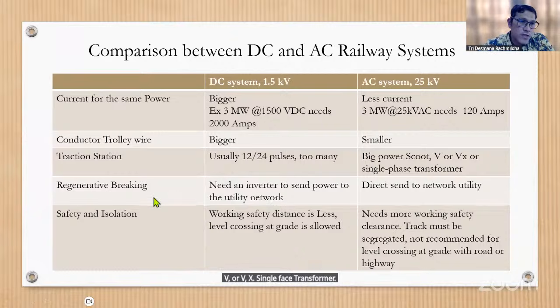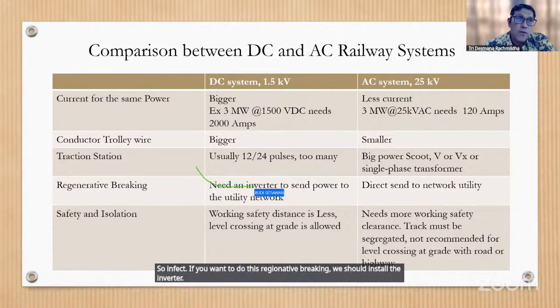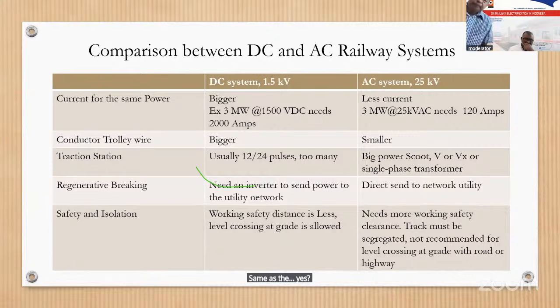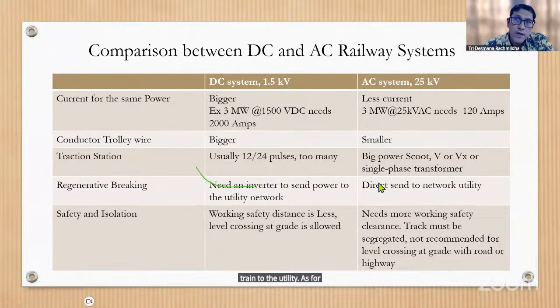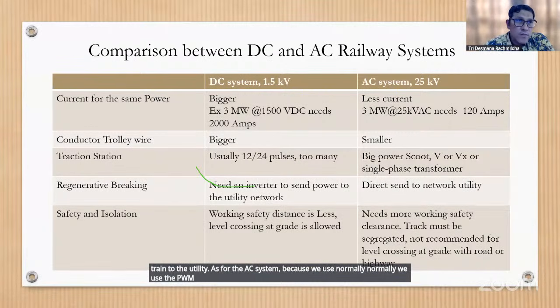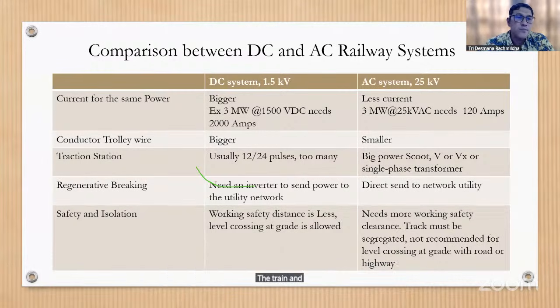And as for regenerative braking in the DC system, because normally we use diode-based rectifiers, it is not possible to do regenerative braking. So in fact, if we want to do regenerative braking, we should install an inverter to send power from the train to the utility. As for the AC system, normally we use PWM rectifiers, PWM converters, so it is possible to have bidirectional power flow between the train and the catenary system.